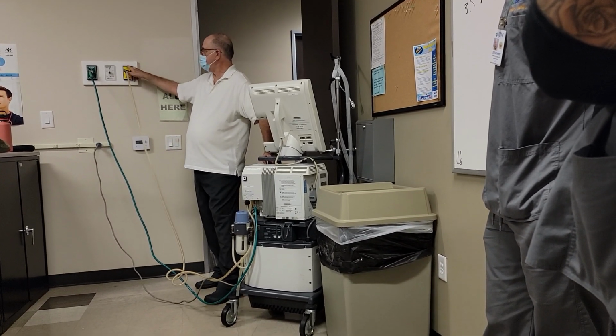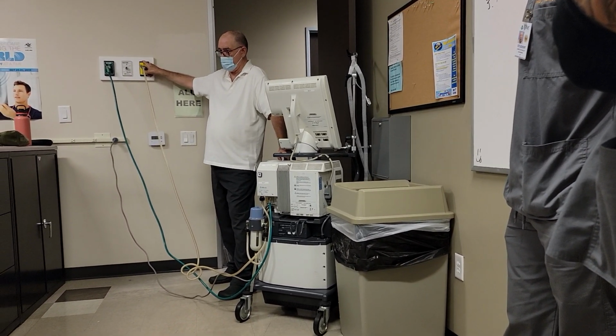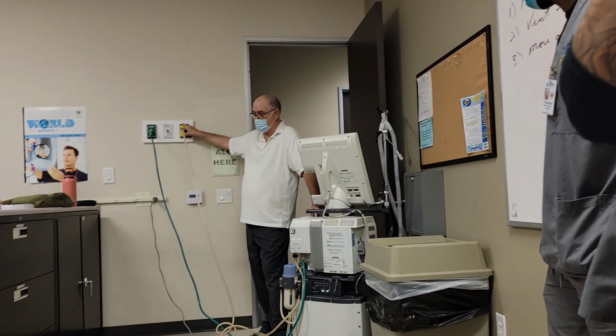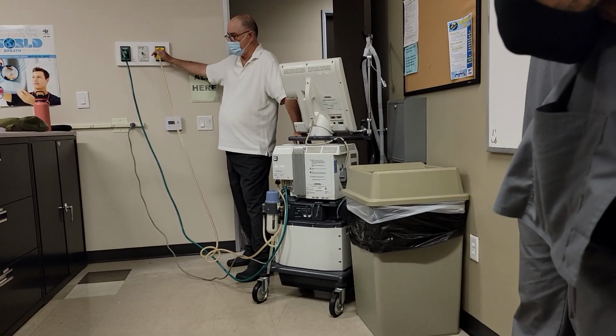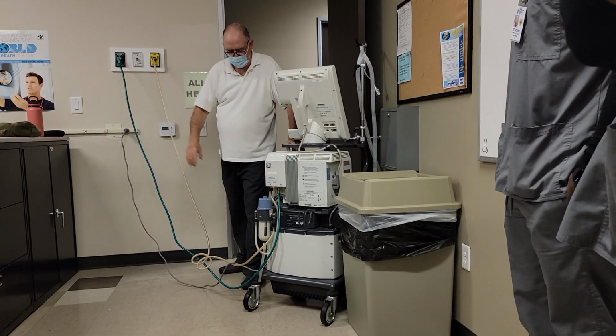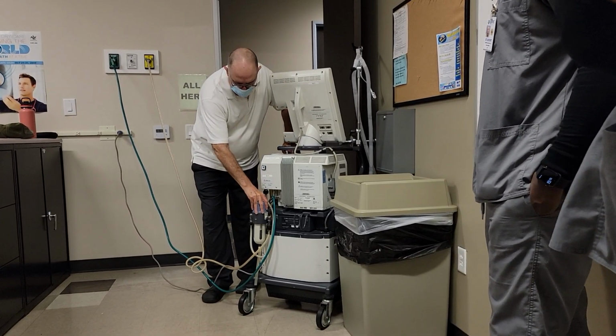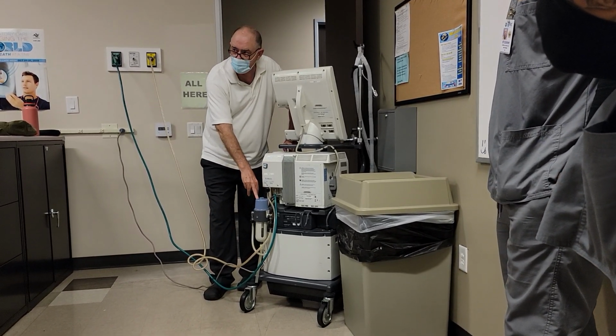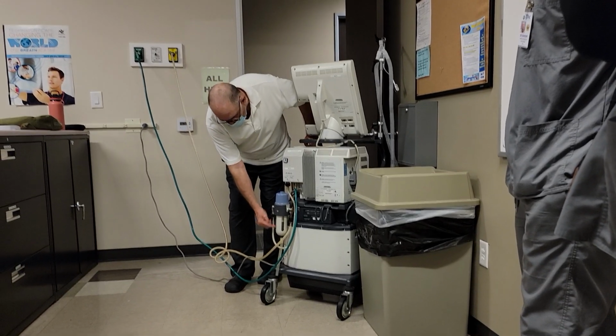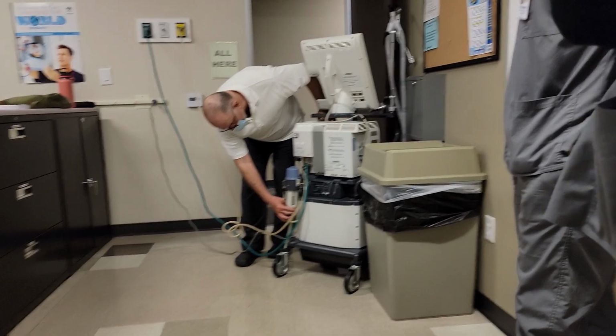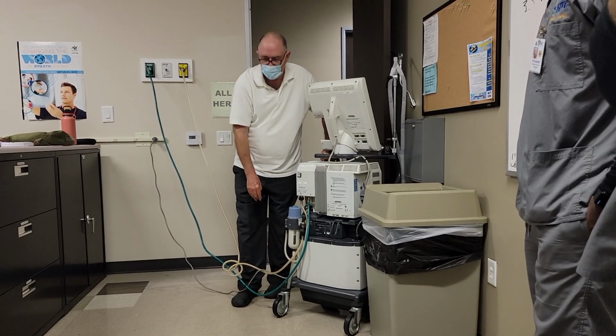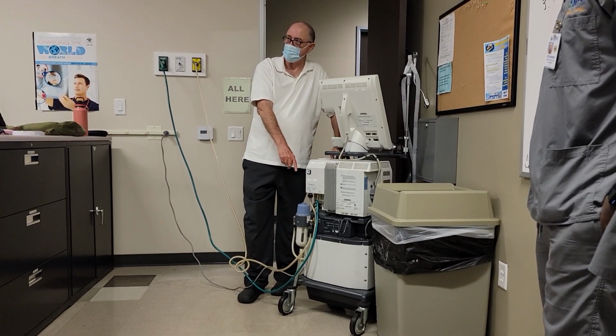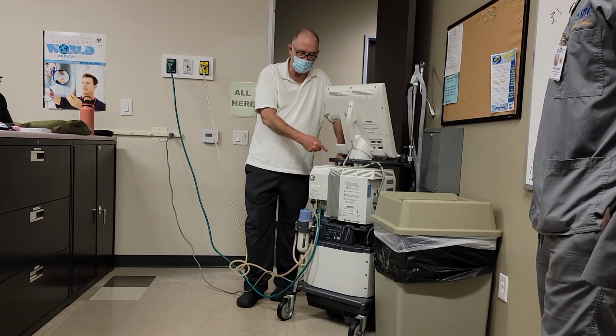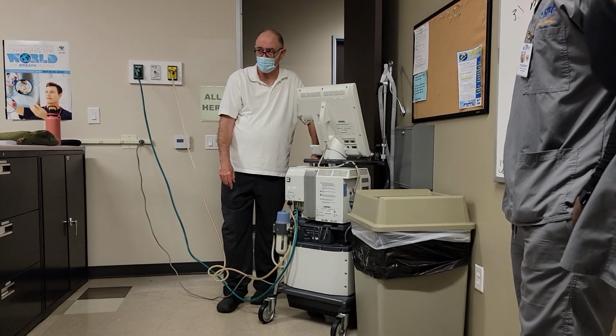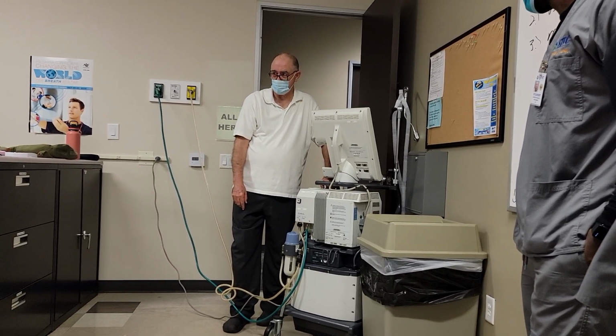So this is 50 pounds per square inch, 50 PSI gas source, air and oxygen, okay? You'll see this system here, that is a dehumidifier. So if you see water in this, there isn't any, be very afraid, okay? Because if that water gets into this, that's about a $5,000 maintenance bill, okay?